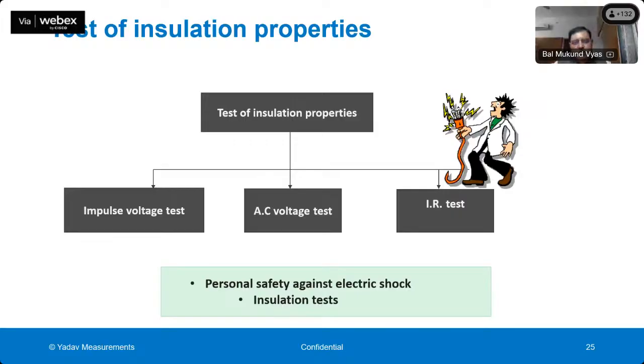Most of the meters used in our houses and mostly in industry have reinforced insulation, which means there is no earthing requirement. The insulation of those meters is tested up to 4 kV as per AC high voltage test requirements. The insulation also has to pass impulse voltage tests, because there can be impulses in the electrical network, and as I told, the electricity meter is the first device which faces all these impulses. So let us see what the different tests are.